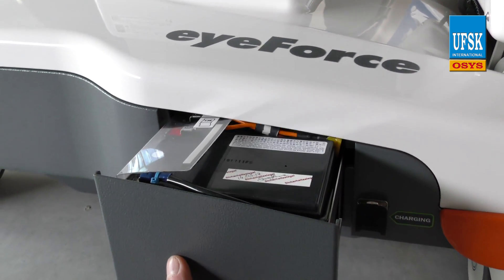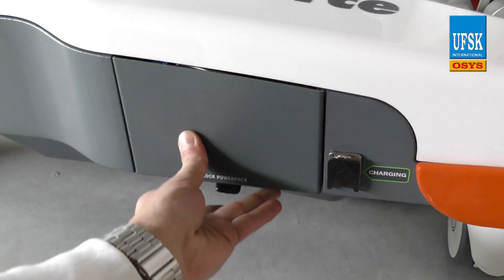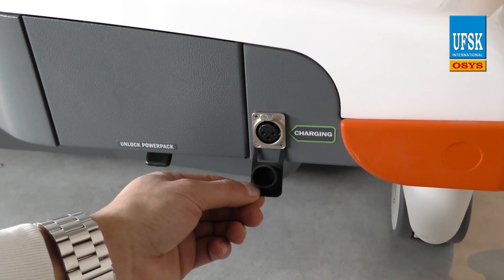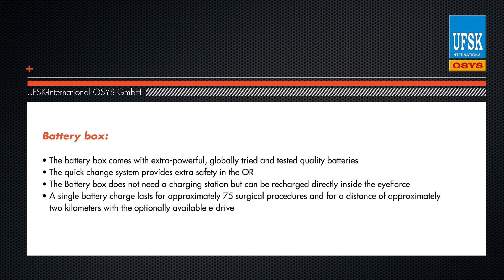The battery box comes with extra powerful, globally tried and tested quality batteries. The quick change system provides extra safety in the OR. The battery box does not need a charging station, but can be recharged directly inside the eyeForce. A single battery charge lasts for approximately 75 surgical procedures and for a distance of approximately 2 kilometers with the optionally available eDrive.